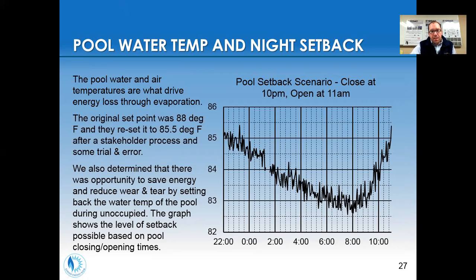So in this case, they looked at changing from a pool set point of 88 to 85.5. This was a pretty warm pool, but it didn't really need to be therapeutic per se. So they were able to do some trial and error and change this pool water set point. And 85.5 is still a very warm pool, but this gets it a lot closer to the air temperature of about 80 degrees. That's a reasonable air temperature, and 2 to 4 degrees is really an ideal difference in a typical pool between the air and water temperature.